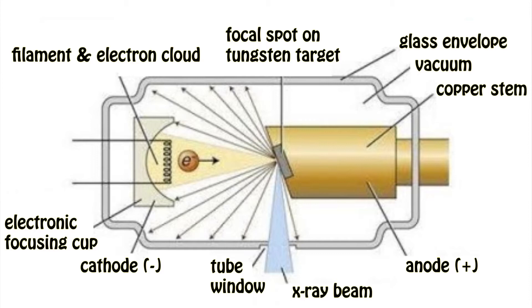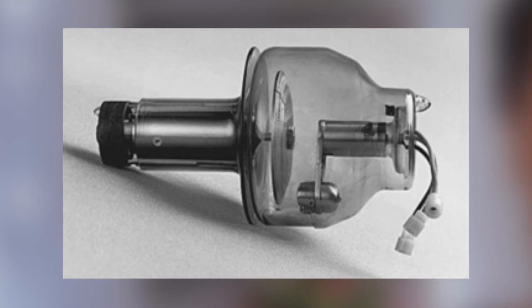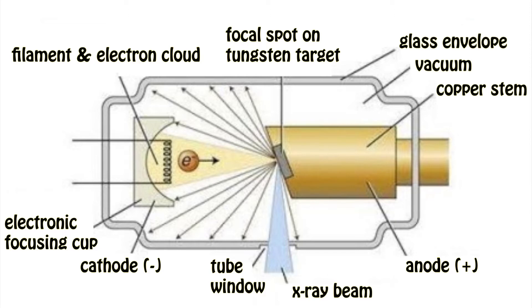Let's get into the structures of the tube in a bit more detail, as they form the basis of our explanation on how x-rays are produced. The structures are contained within the envelope, which provides vacuum, support, and electrical insulation. The envelope is usually made from glass, although some tubes use ceramic or metal. Also not pictured in the diagram, there is insulating oil, which carries heat produced by the anode away via conduction.